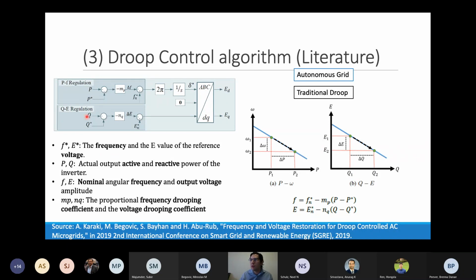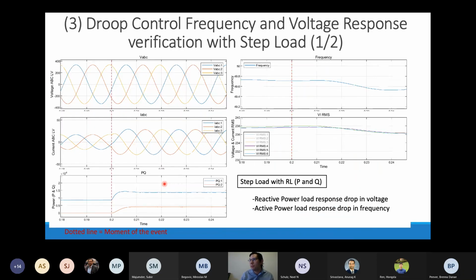Here I mentioned the portions of the droop control that we are utilizing: the frequency, the reference voltage, and the active and reactive power, and how active power relates to the frequency and reactive power to the voltage, and how the frequency can step down. Here I'm proving how the droop control is reacting to a step type of load. As we can see, the load happens here. In the right-hand side figure I will just show the frequency and the voltage in RMS for better understanding. So when the load kicks in and it's an active and reactive load, we have a small drop in the frequency, and also a small drop in the voltage, and then we continue to steady state.